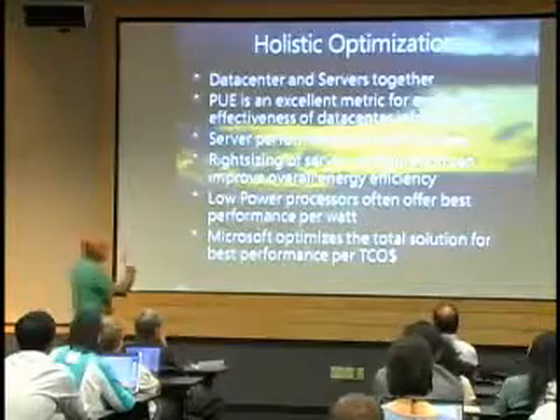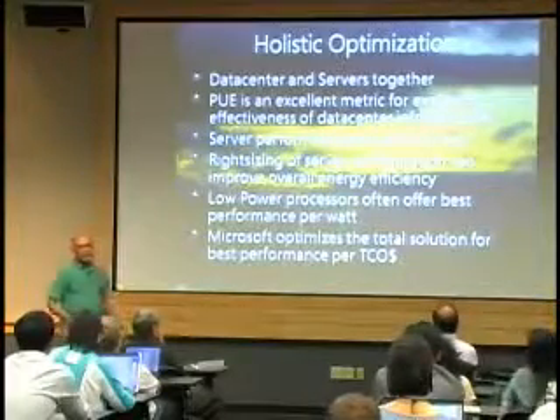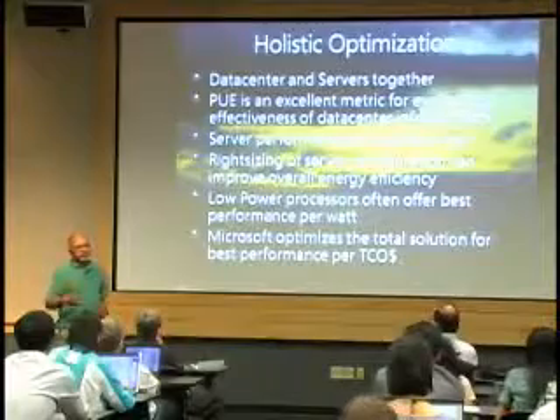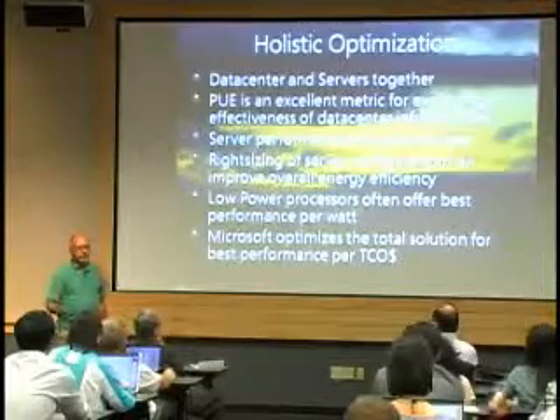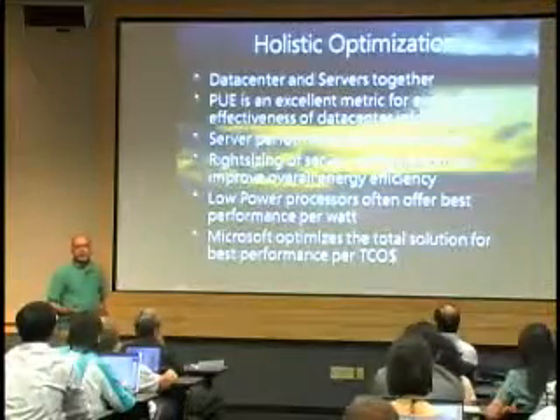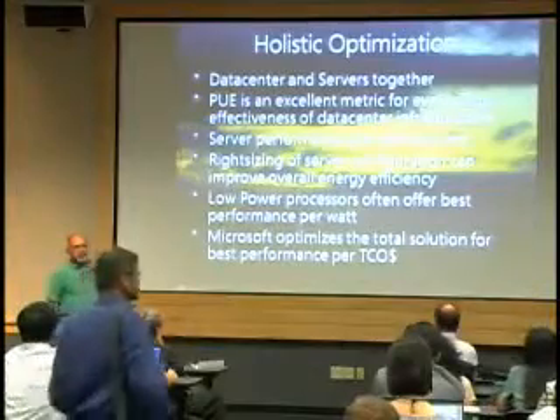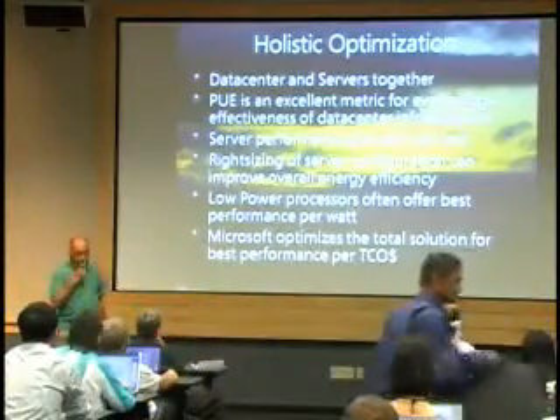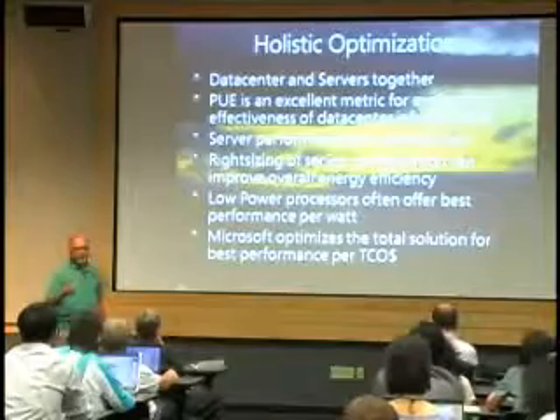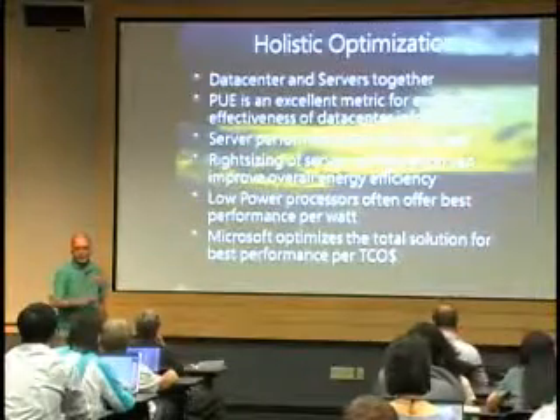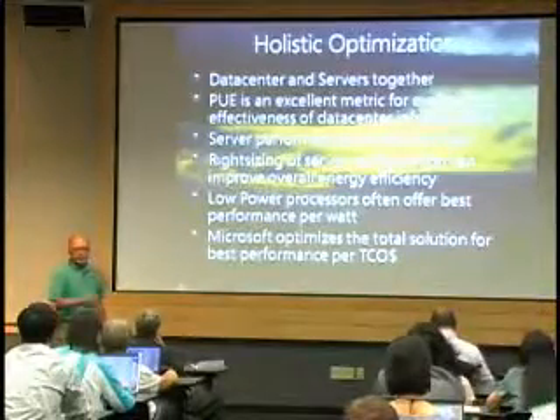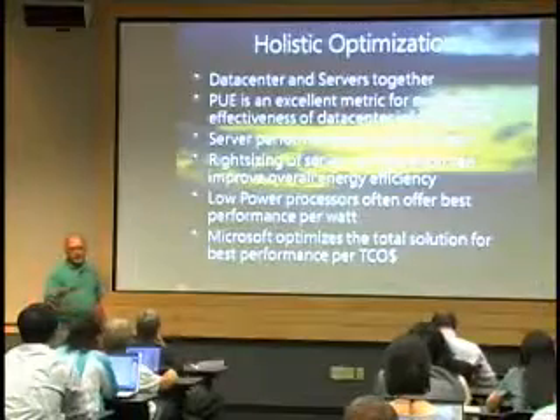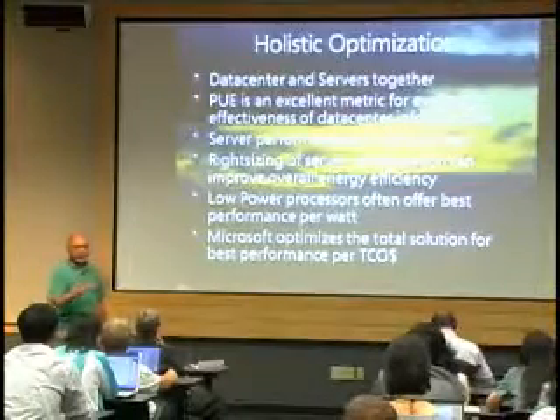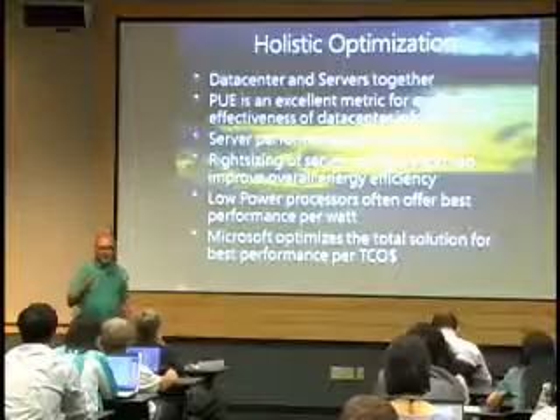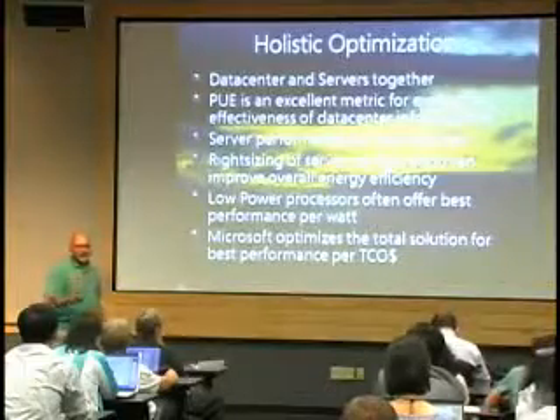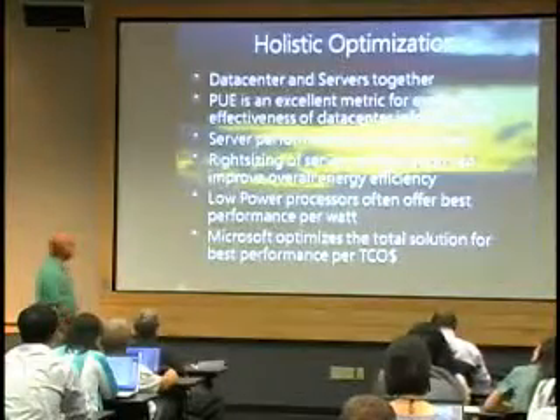The PUE is an excellent metric, and it's good to track historically how well you're doing. But blindly looking at PUE doesn't work. For example, in the PUE calculation, the power consumed by the fans in the server is part of the IT load. Now, if I have a design in which I remove the fans from the servers, the server power goes down, and my PUE gets worse because the server power went down. So if you blindly apply something like PUE, it doesn't work that well.